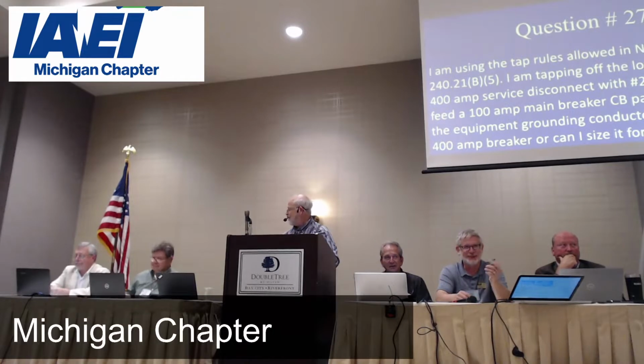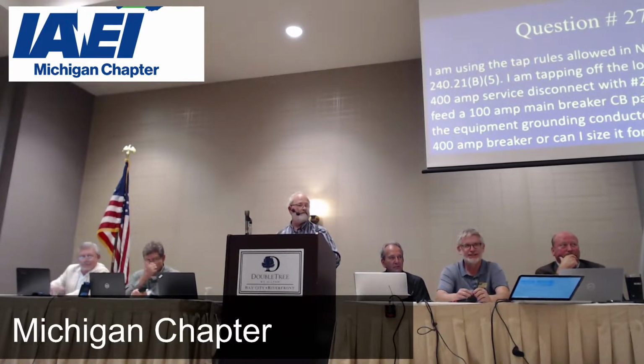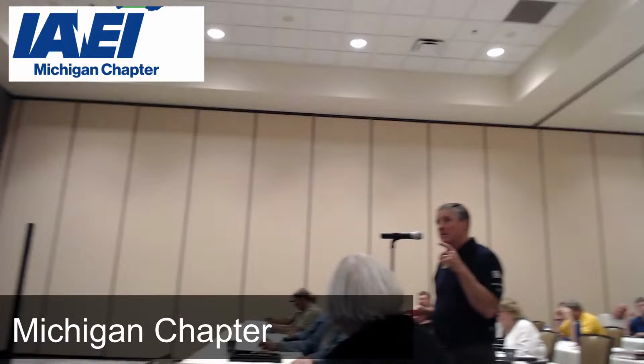Good job. Okay. Oh, go ahead. If the fault is between the two, we're not going to see current going through the 100 amp breaker. No, not at all. We've got to clear the 400 amp breaker. Yeah. Tap conductors, we protect from short circuit and ground fault with the larger upstream device, and overload with the lower downstream. Yeah, so we've got to use the 400 amp.